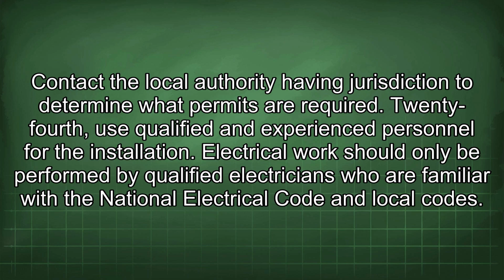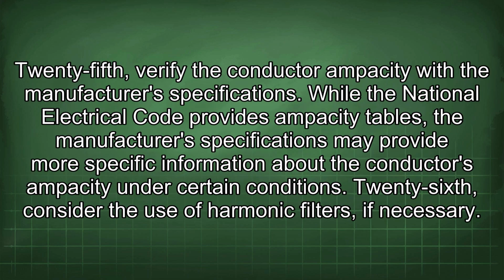24th, use qualified and experienced personnel for the installation. Electrical work should only be performed by qualified electricians who are familiar with the National Electrical Code and local codes. 25th, verify the conductor ampacity with the manufacturer's specifications.